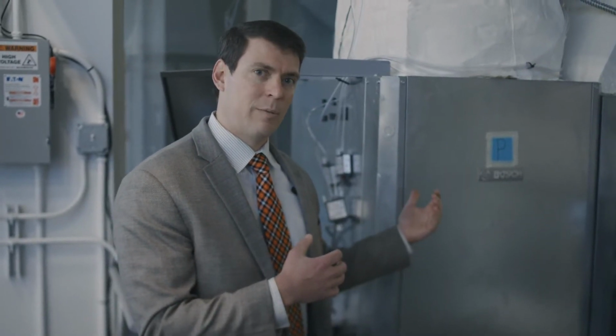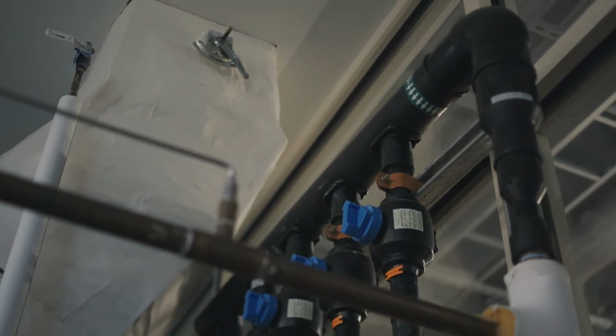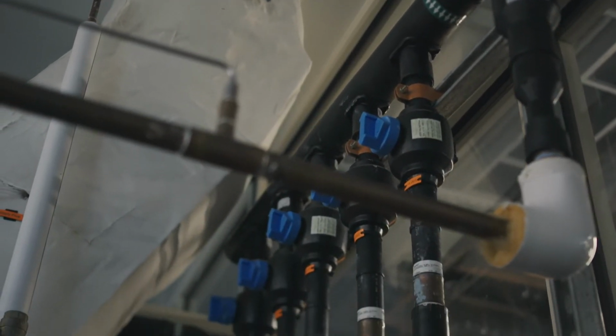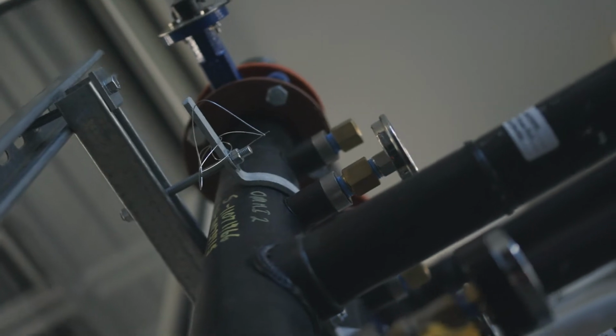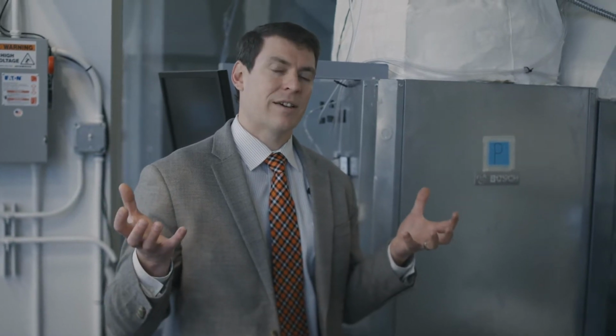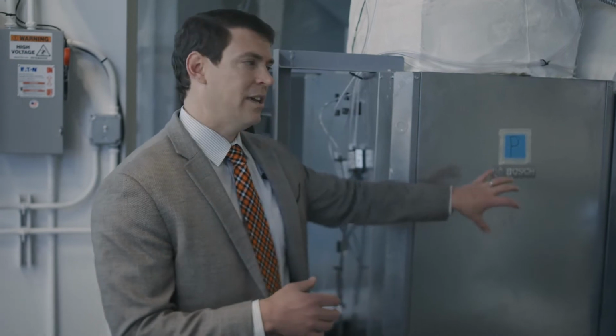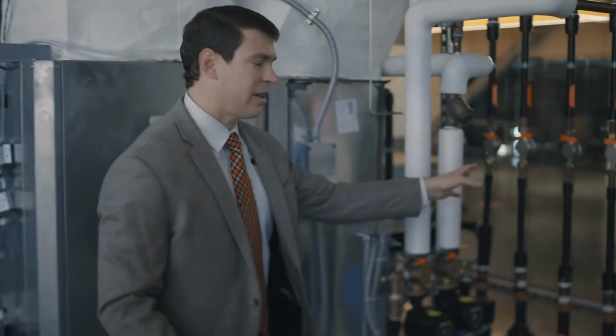There's a separate heat exchanger extracting heat from the ground through what are called boreholes. The boreholes are very deep holes into the ground where the temperature is very consistent throughout the year. So in the wintertime, like now, it's much warmer underground than the air is outside today, so you can pull heat into these boreholes and transfer it into this vapor compression cycle. You can see the boreholes coming out of the ground here.